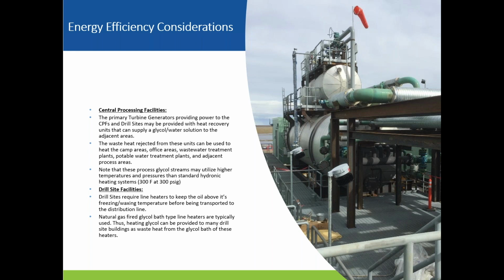On the drill sites, we have production heaters or line heaters because we have to keep the oil going down the pipeline, keep it above its waxing temperature. So those generally have a glycol bath on them. Those are a little lower pressure and temperature than the HRU systems, more of a typical commercial type glycol pressure, but we can use those. We aren't using those as much as we used to. It's a lot more expensive to put in all the glycol piping throughout the drill sites than it is to put electric heat in. But it's an option. It's something to be considered during the early design phases.